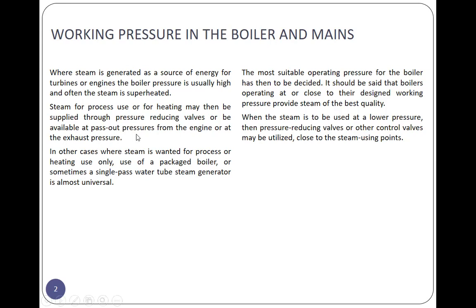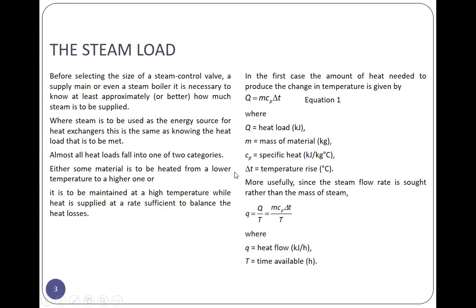Animation. Okay, the steam load. Before selecting the size of a steam control valve, supply main or even a steam boiler, it is necessary to know at least approximately or better how much steam is supplied. So where steam is to be used as the energy source for heat exchanger, this is the same as knowing the heat load that is to be met.